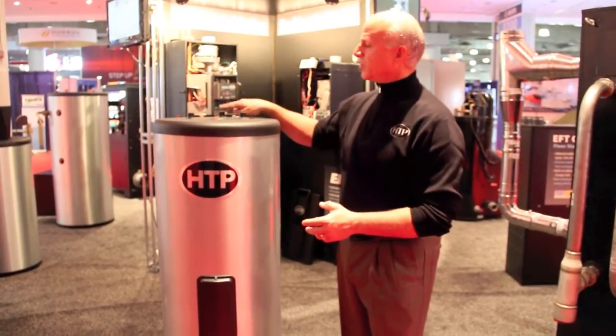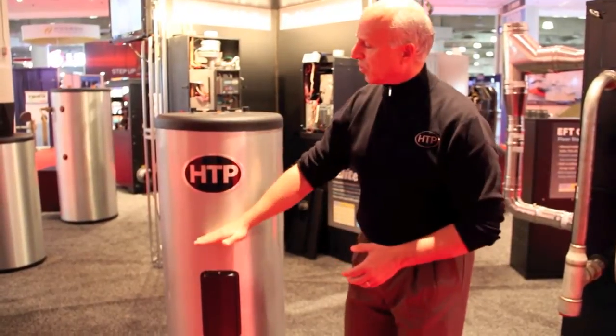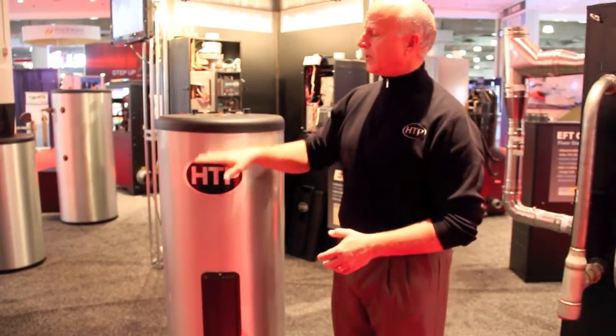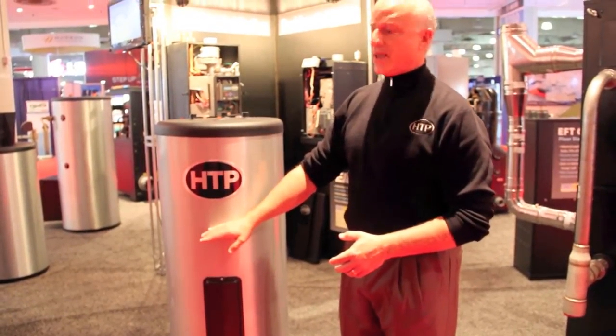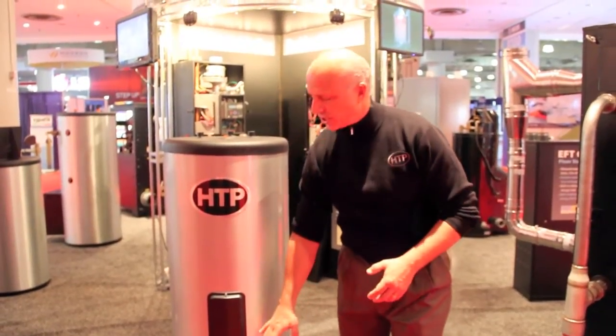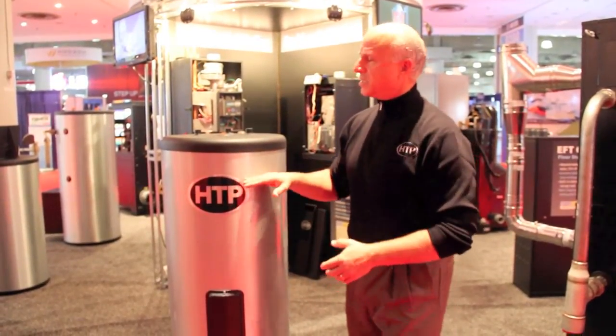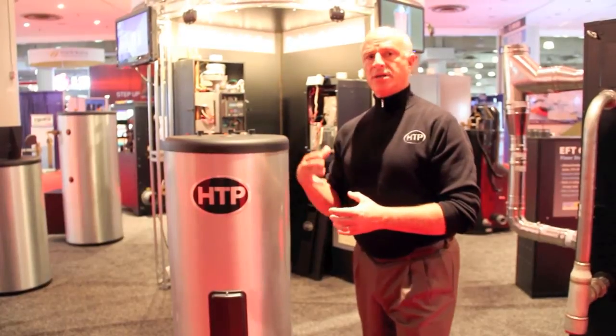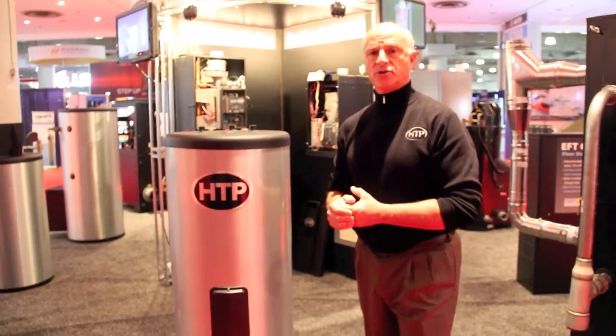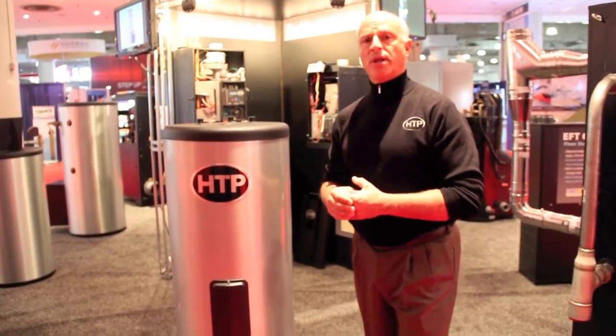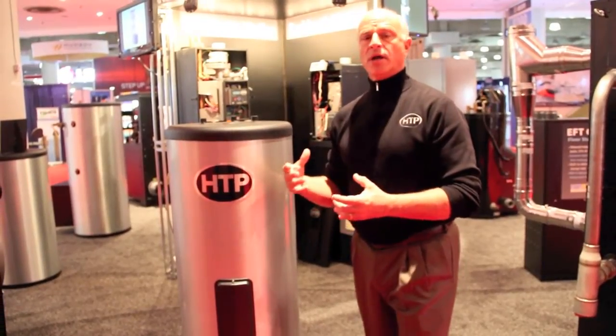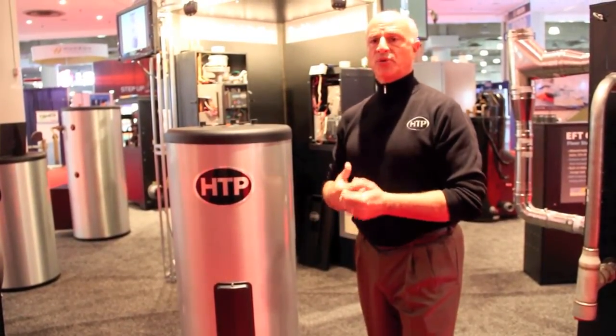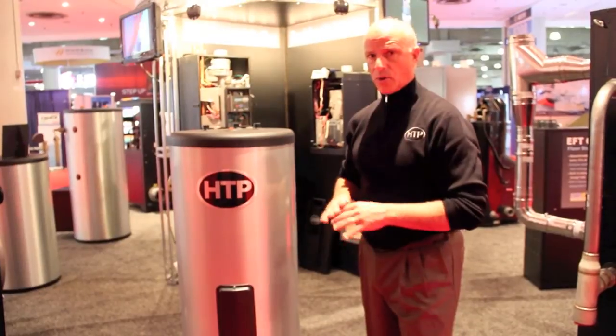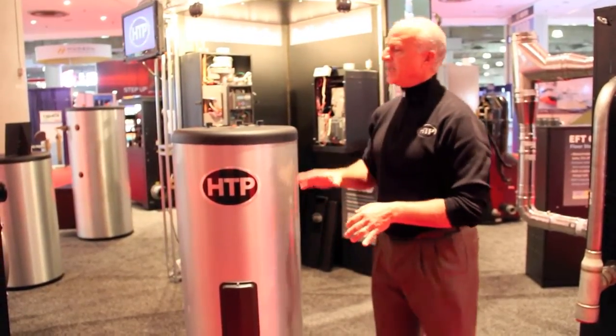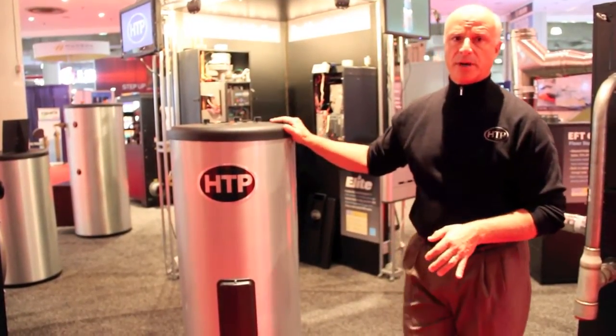By utilizing this recirc port, we're only circulating the water through the quadrant on the top here, and then we're basically dissipating energy on the bottom. When it does turn on the heater as it sees the temperature drop, it gives the boilers a longer cycle run at a lower temperature, which improves the overall efficiency of the whole hydronic system and really makes this product unique in the marketplace.